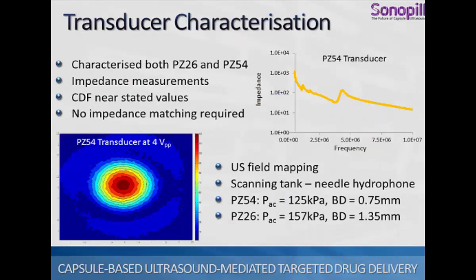So to get more details about the transducers, we've carried out some characterization. So we characterized both PZ26 and PZ54. So we carried out some electrical impedance spectroscopy measurements and found the central driving frequency of both transducers was near that stated by the manufacturer, which was a bonus. And there was no impedance matching required either. So we then carried out some ultrasound field mapping. This was done in an acoustic scanning tank with a needle hydrophone moved about in the ultrasound plane. So you can see the pressure map here.